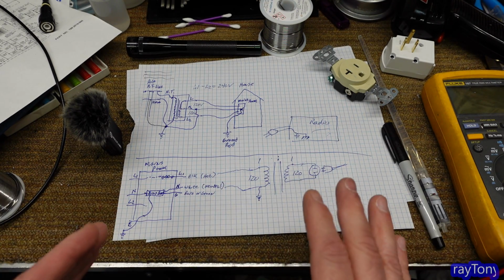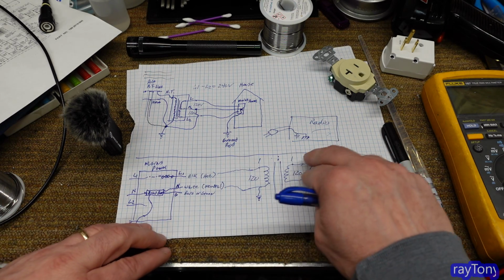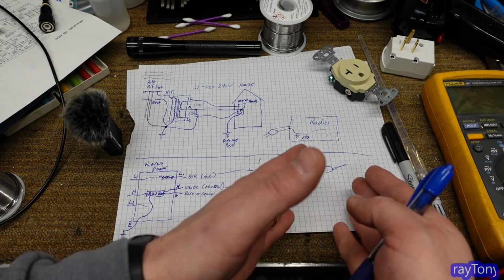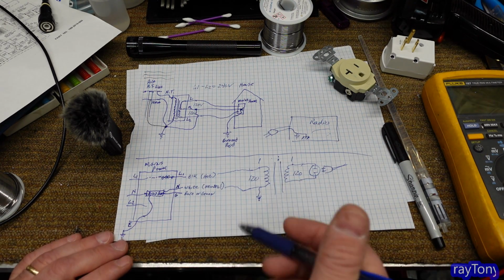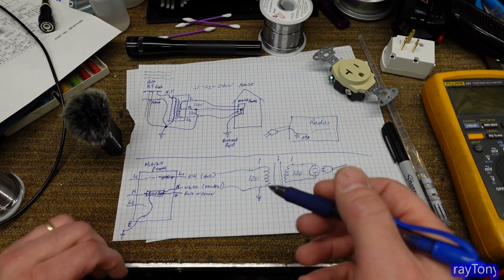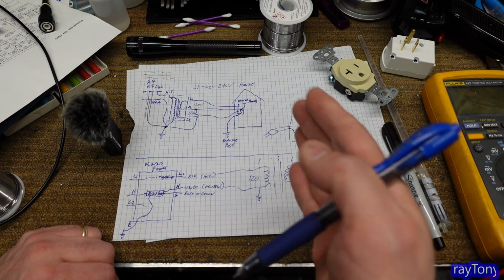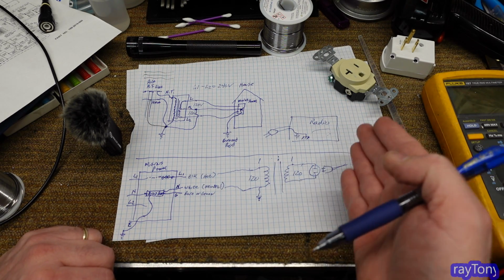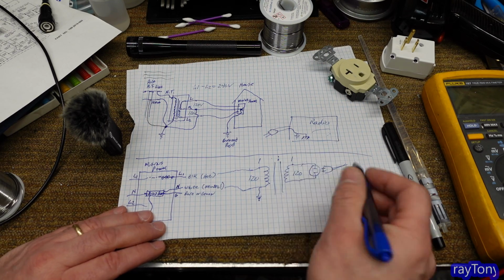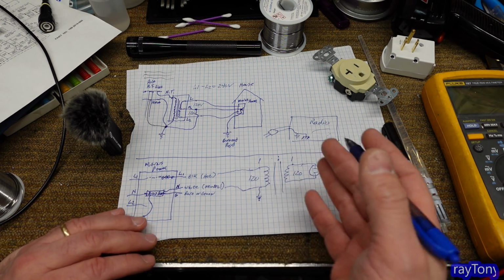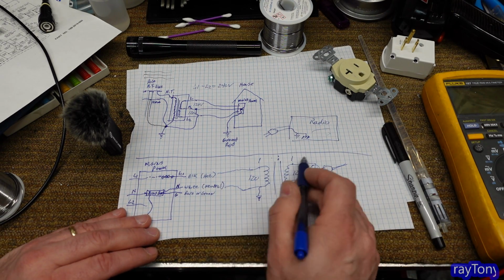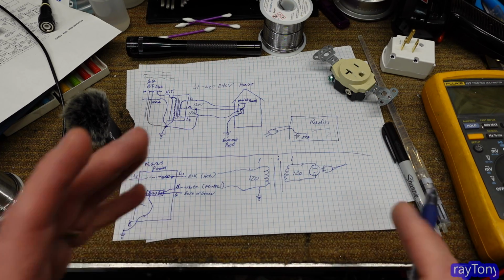It's not totally safe still, because you still have 120 volts inside the radio and you can still get shocked. But what it's going to prevent is your test equipment or anything connected to neutral and ground from causing a ground loop and causing a short, or making live mains on the chassis. I hope that makes sense.